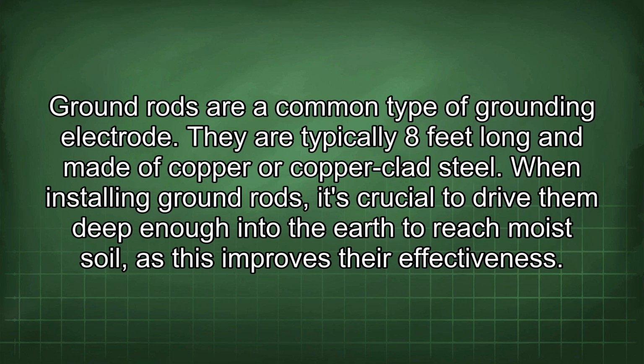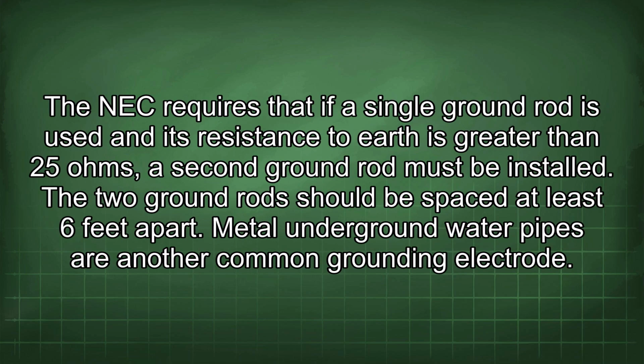Ground rods are a common type of grounding electrode. They are typically 8 feet long and made of copper or copper-clad steel. When installing ground rods, it's crucial to drive them deep enough into the earth to reach moist soil, as this improves their effectiveness. The NEC requires that if a single ground rod is used and its resistance to earth is greater than 25 ohms, a second ground rod must be installed. The two ground rods should be spaced at least 6 feet apart.